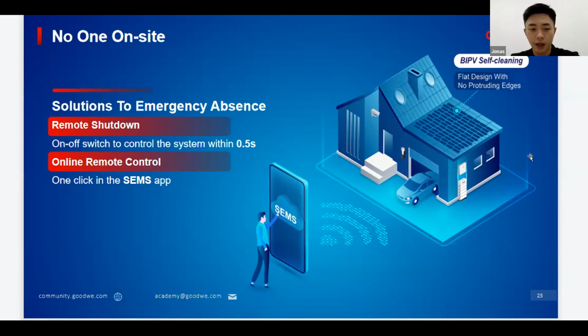The first function we can realize is that the on-off switch can be deployed in a remote place where the operator can turn the switch on or off at a safe distance to control the inverter. Communication cables such as RS485 connect the inverter and switch to transmit signals for remote shutdown. Similar to the principle of remote shutdown, the GoodWe monitoring platform, SEMS Portal, is a totally free platform for customers to monitor whole PV plants. It integrates shutdown and some control functions. With one click on the website, the GoodWe cloud server will send a signal to the inverter via the communication tools and shut down the inverter on the AC side within minutes.